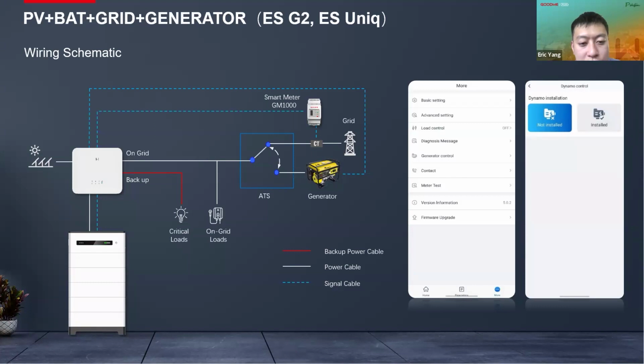It will support the on-grid loads, of course. And also, it can support the backup loads through the inverter bypass, as in the diagram. So the power goes from the generator to the inverter on-grid side, and then through the inverter to the backup side to support the backup loads. And also, if the customer wants the generator to charge the battery, we can realize it. The generator power can support both the on-grid load and the backup load, and also it can charge the battery.